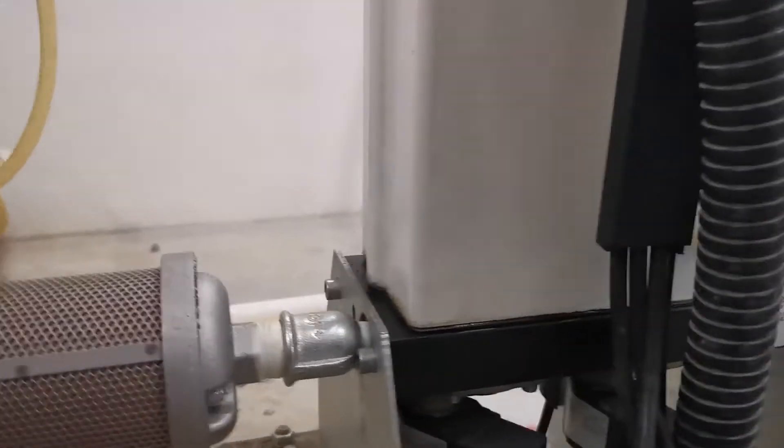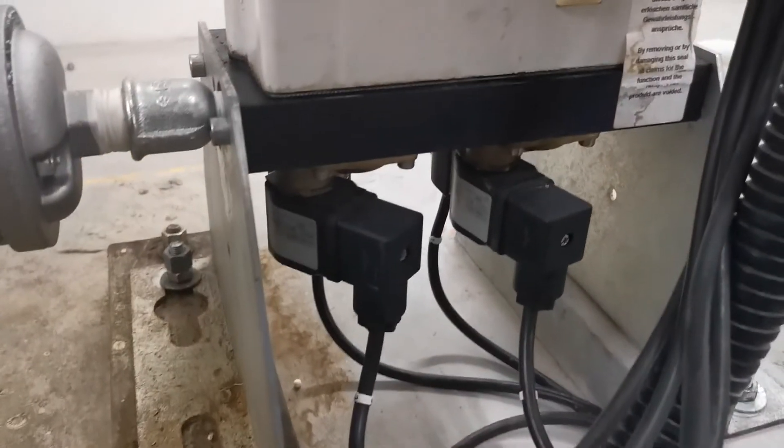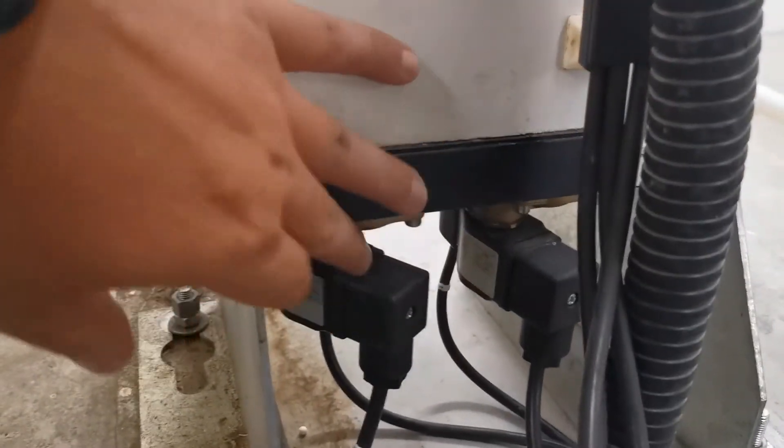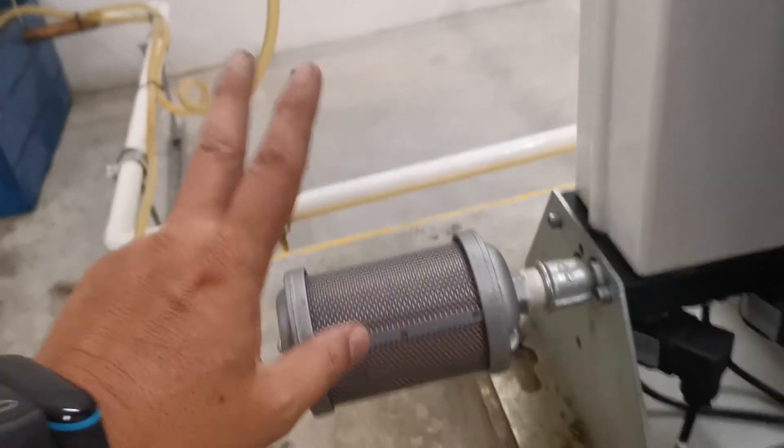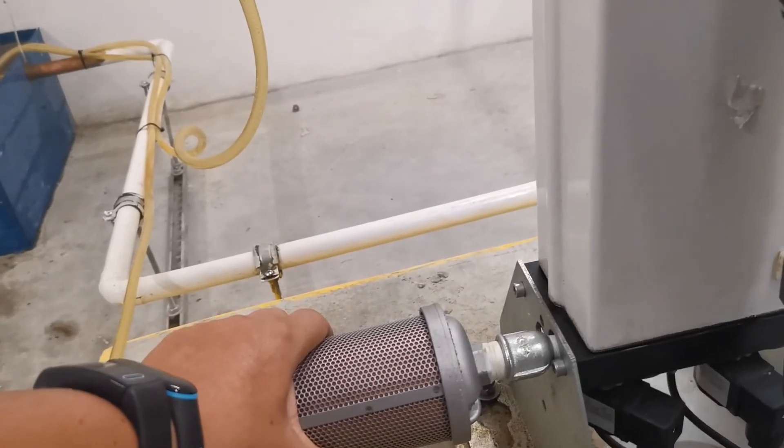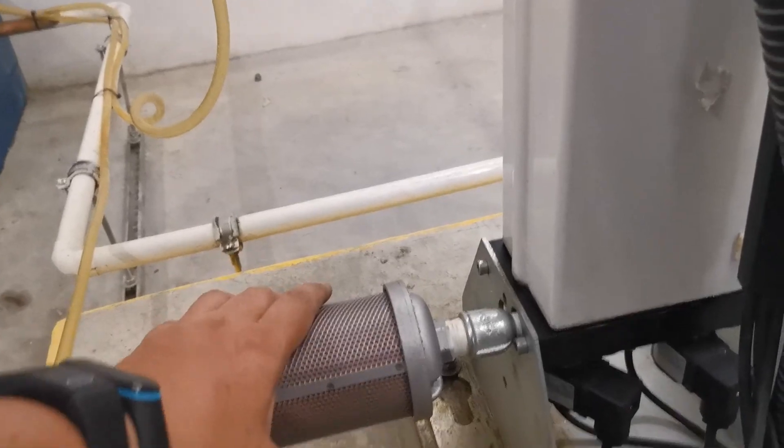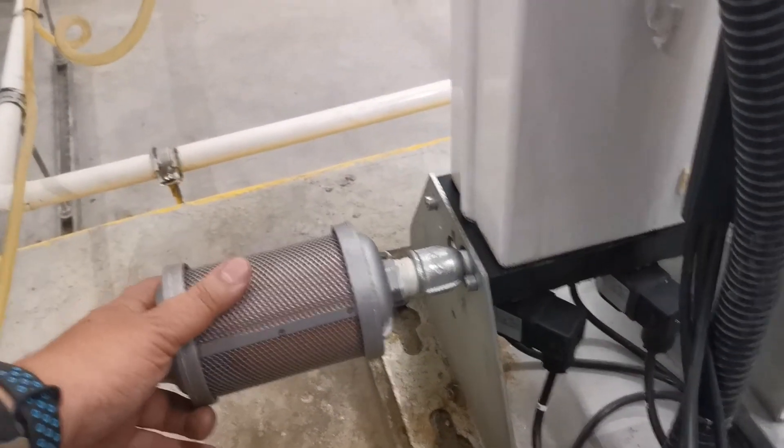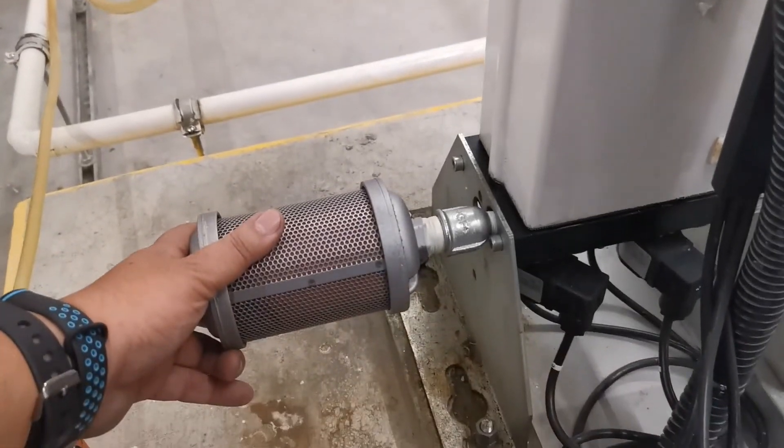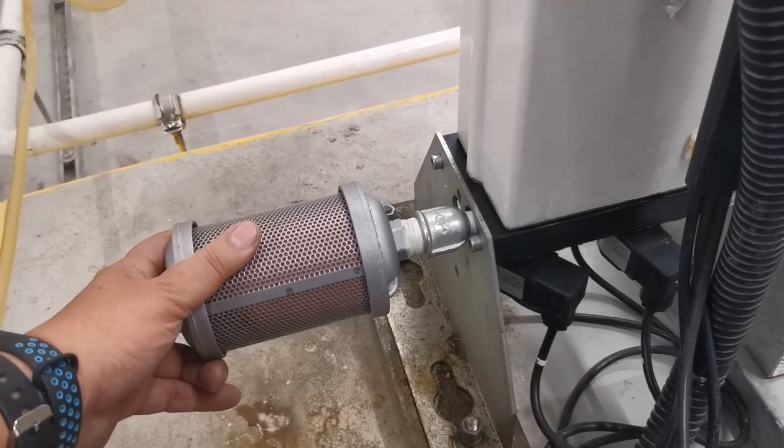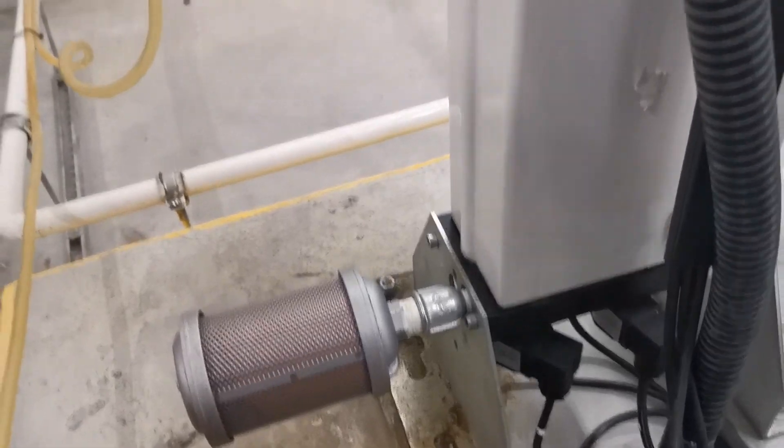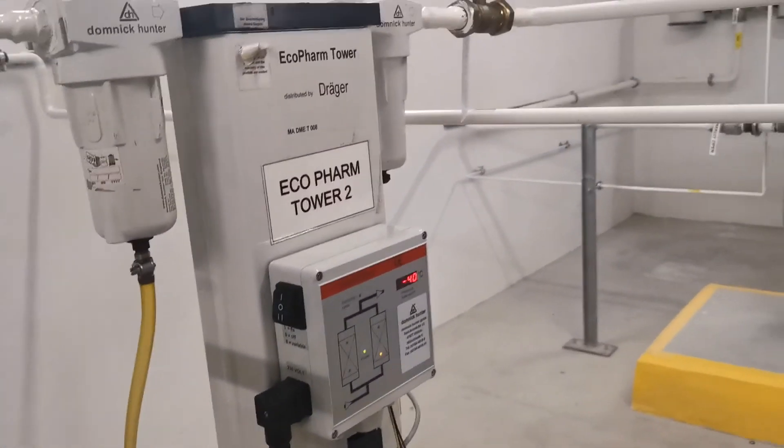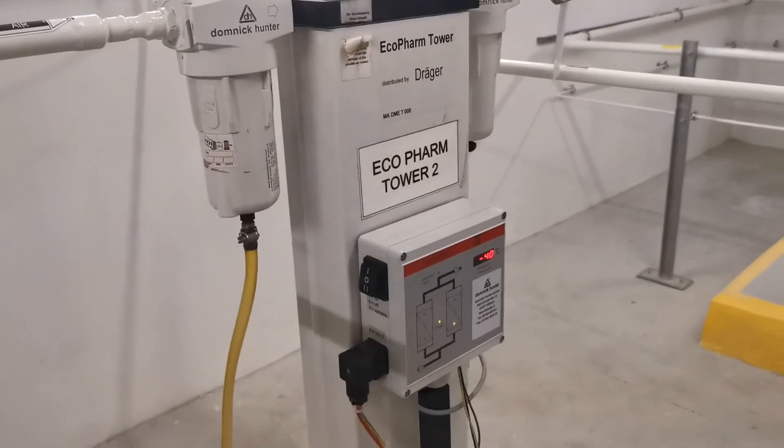Generally, you will have solenoid valves that control the inlet and the exhaust, and of course you have exhaust for all the moisture that was collected. Usually we will put a silencer or sound absorber on the exhaust because when it does go, it can be quite loud. So generally that's how a desiccant dryer works, and thank you for watching.